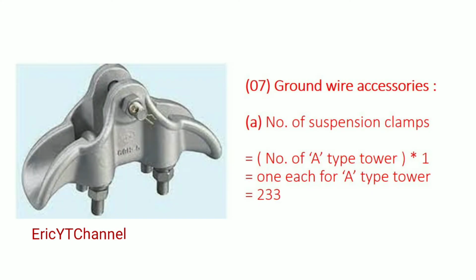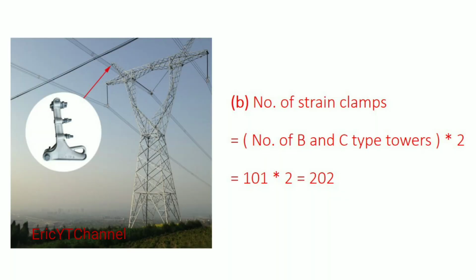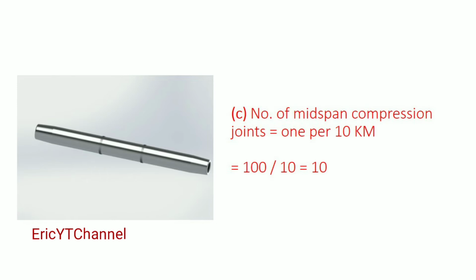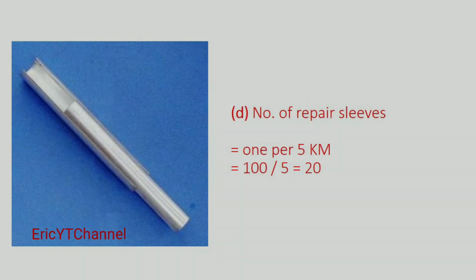Number 7 is ground wire accessories. Letter A is number of suspension clamps equals number of A-type towers times 1, equals 1 each for A-type tower, equals 233. Letter B is number of strain clamps equals number of B and C type towers times 2 equals 101 times 2 equals 202. Letter C is number of mid-span compression joints equals 1 per 10 km equals 100 divided by 10 equals 10. Letter D is number of repair sleeves equals 1 per 5 km equals 100 divided by 5 equals 20.